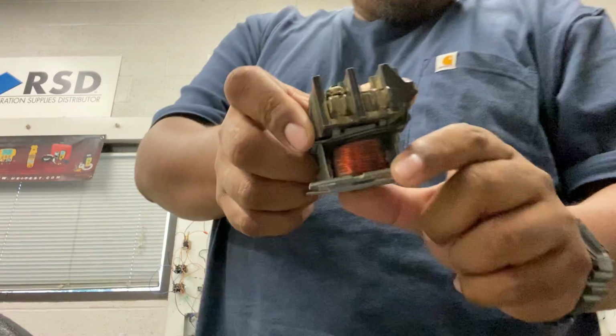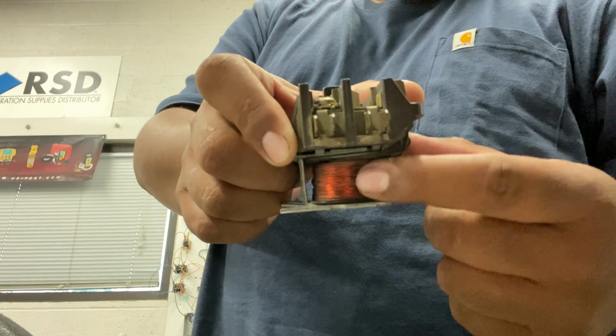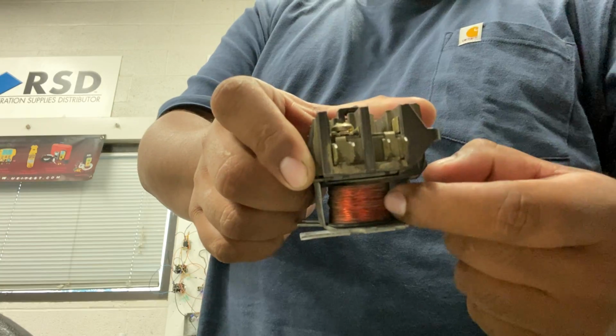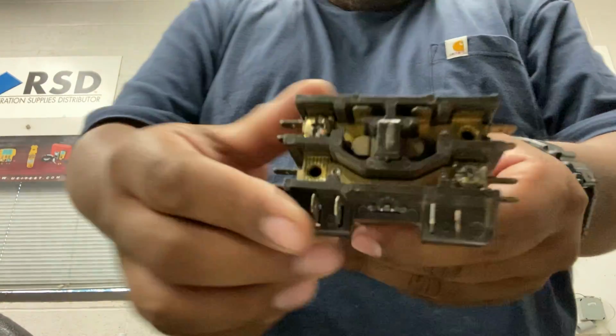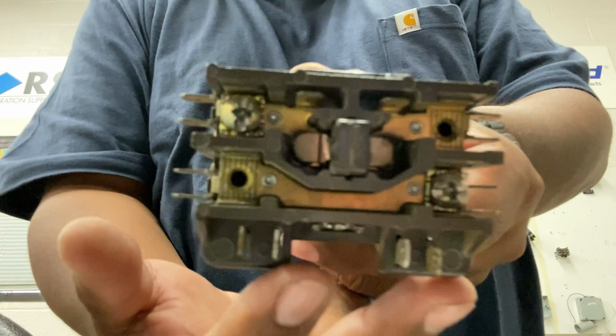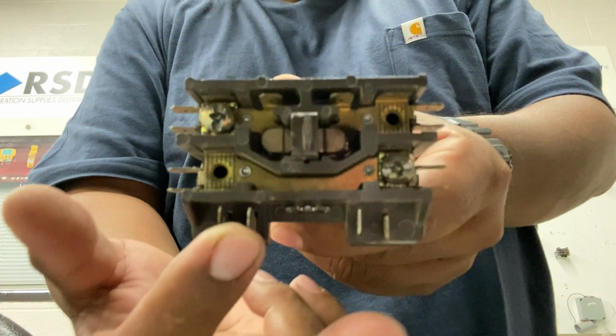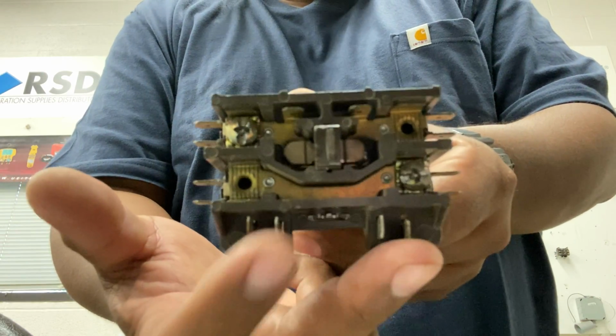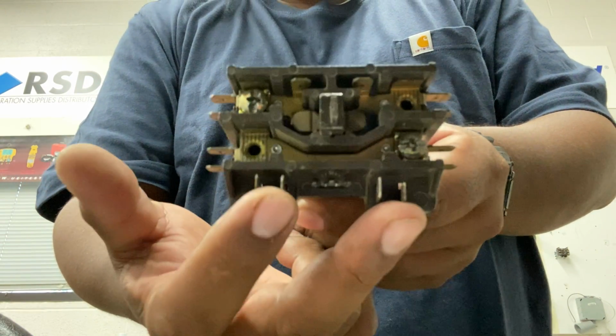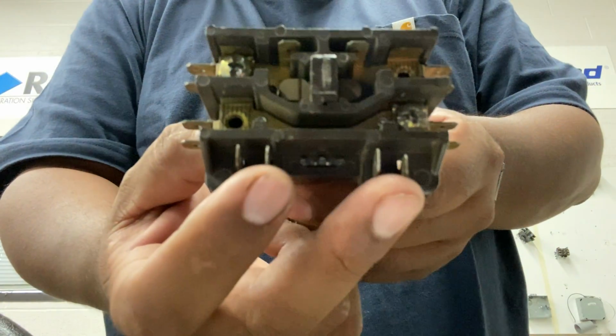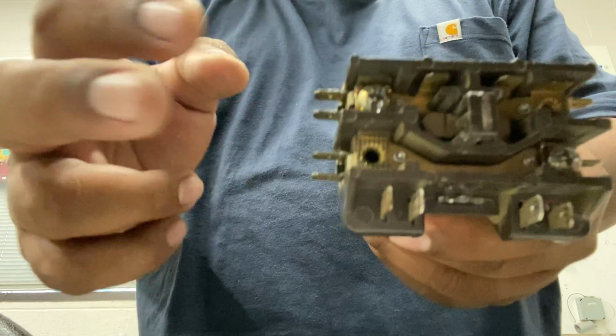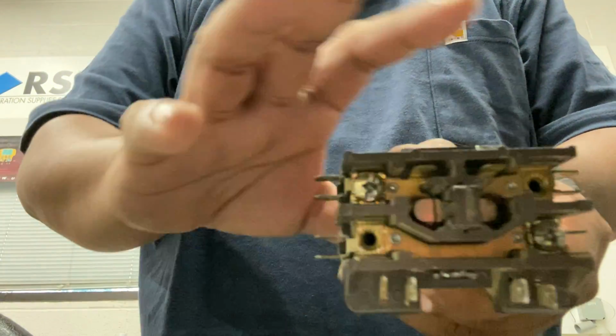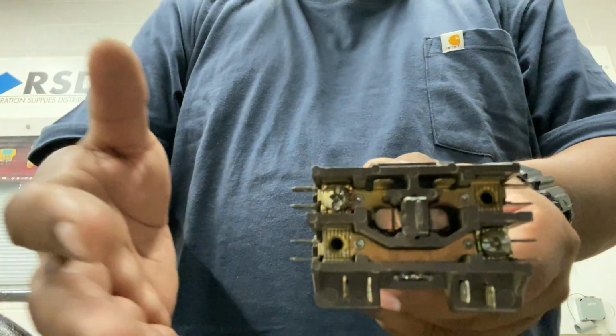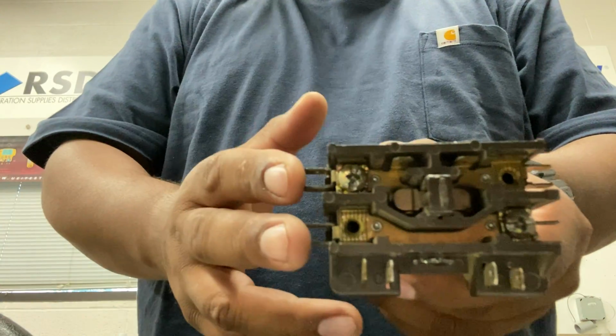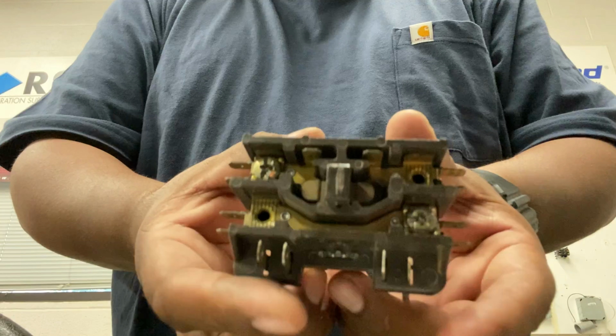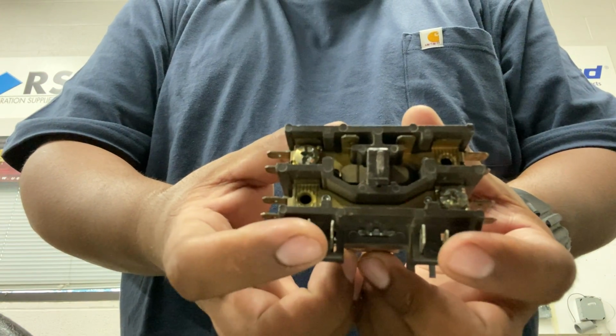And then you guys can see down here, all these strands of copper. This is actually the coil. So what happens is, like I said, you guys have incoming power coming here. Then down here, you actually have a positive and negative, however you guys want to connect it. It doesn't really matter as long as you have a positive and a negative on this side. Down here is actually going to be 24 volts. Over here, you're going to operate anywhere from 110, 208, 240. On bigger contactors, you're going to be operating 460 three-phase power. But for this guy here, it's going to be 208 volts. But down here, we're actually going to operate on 24 volts, right?